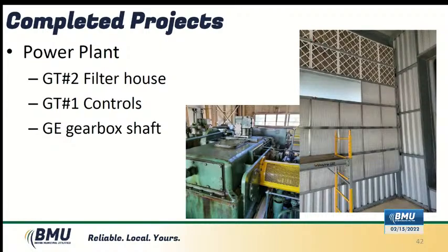From the powerhouse, we also changed the G2 filters at the top. Every two to three years there's a $2,000 or $3,000 bill to change those. The ones at the bottom are metal and cost about $4,000, but we can just wash them off. With the water line we're going to have out there, we can pull them out, power wash them, and put them right back in, and they'll do just fine. All we need to do is keep the big junk out of the generator — it doesn't need to be filtered like a furnace.